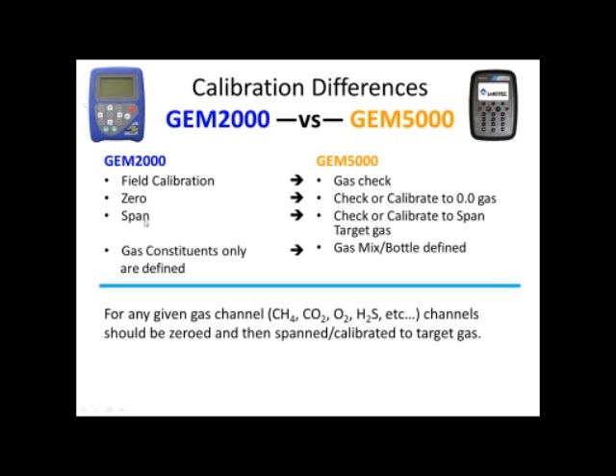The zero and the span on the GEM2000 will be the equivalent to a check or calibrate to zero gas and a check or calibrate to span target gas for the GEM5000. And in short, the concept is still the same. Before we can calibrate a specific channel, we'll still need to zero it out before we calibrate. So this is just basic terminology to be aware of, so you don't get confused during the calibration process.